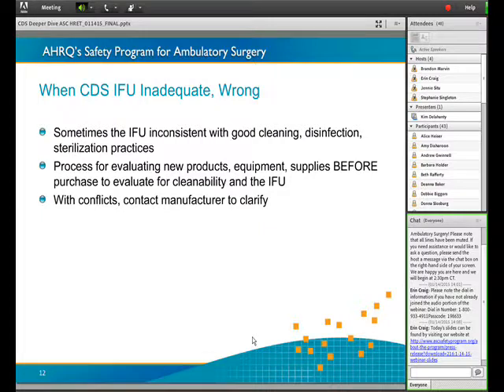Again, an arthroscopic shaver is still dirty after cleaning following the IFU for probe disinfection. So what happens is the IFU says, here's the situation, here's how you clean it. Even after cleaning, these shavers still had bioburden on them, because they were asking them to use pop-up wipes that were not effective for getting that biofilm off. The scope manufacturer recommended cleaning with Hibiclens, which is an antiseptic for use on skin, not on instruments.